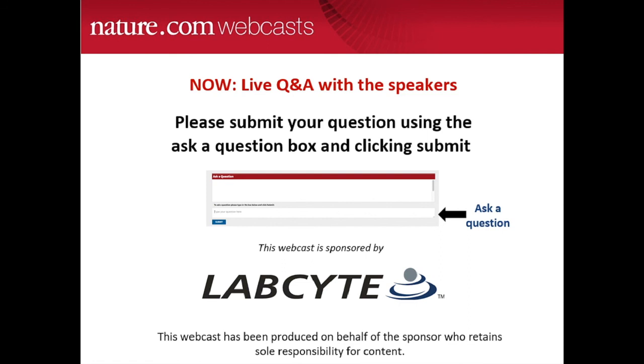When customers first start with the echo, that is an area of concern on their part. And we commonly just recommend that they do a test run with a particular plate and fluid type that they're using, turn it over, tap it on the bench above a Kim wipe or something like that, and just confirm that nothing falls out at the volumes that they're working with. But I will say very quickly they get comfortable with the ability of the plates to retain that. What will obviously affect the surface tension are some of the common additives. So, for example, surfactant will lower that surface tension. And so one just needs to be a little bit careful and confirm that the volumes are not going to result in any liquid dripping out. But commonly, the volumes that we're working with do not cause any issues there.